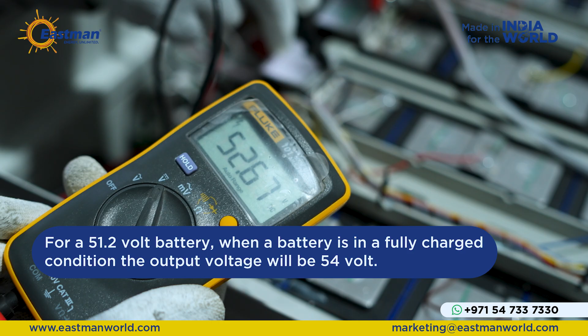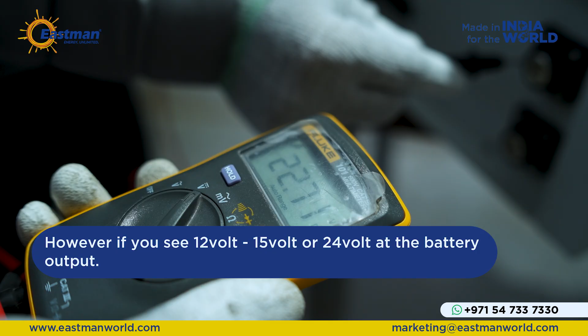For a 51.2 volt battery, when the battery is in a fully charged condition, the output voltage will be at least 54 volt. However, if you see 12 volt, 15 volt or 24 volt at the battery output, it is a clear indication that the issue is from the BMS.